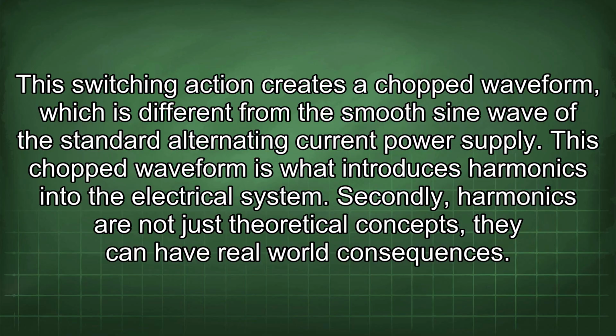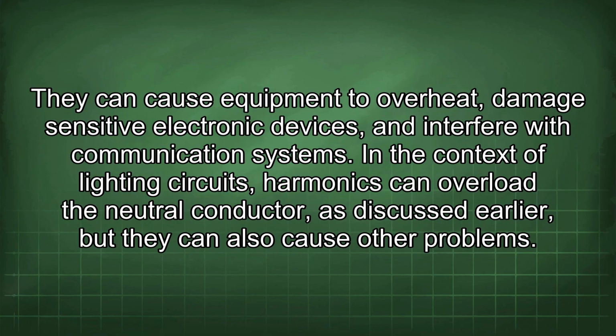Secondly, harmonics are not just theoretical concepts, they can have real-world consequences. They can cause equipment to overheat, damage sensitive electronic devices, and interfere with communication systems. In the context of lighting circuits, harmonics can overload the neutral conductor, as discussed earlier, but they can also cause other problems.